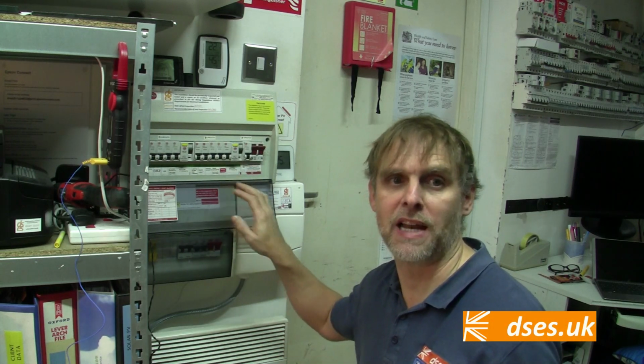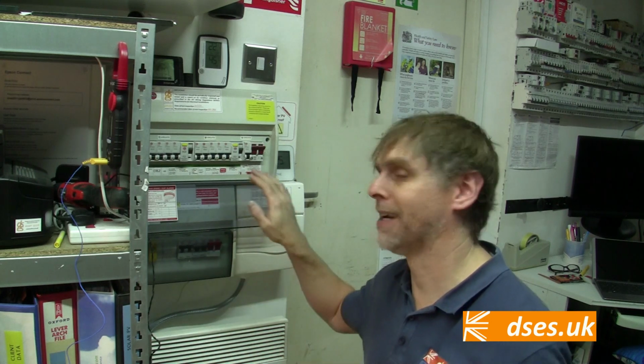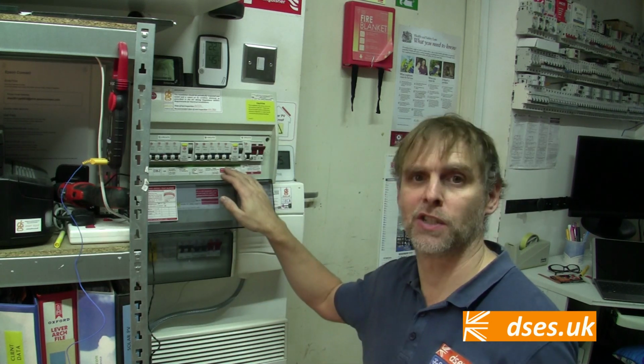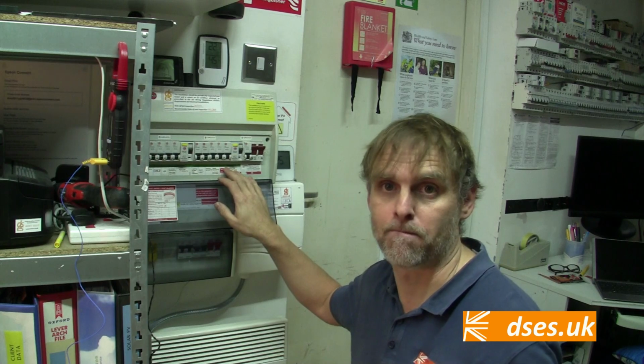So, will retrofitting arc fault detection result in any new tripping trouble that my existing overcurrent and earth leakage protection isn't otherwise upset by? Before I begin the upgrade, I'm going to undertake a wholly new and very thorough bout of inspection and testing to repeat that of 8 years ago, and to compare the numbers to see what's changed.